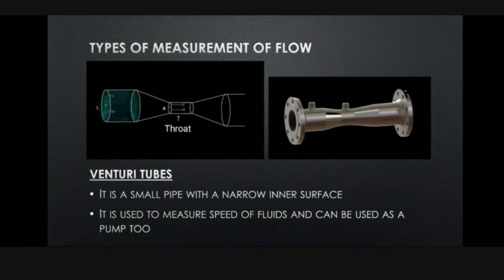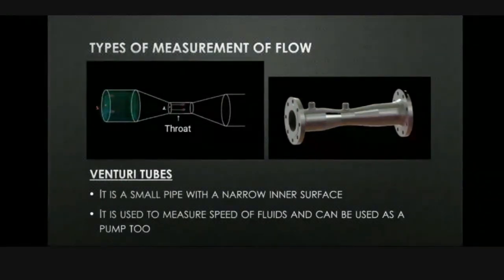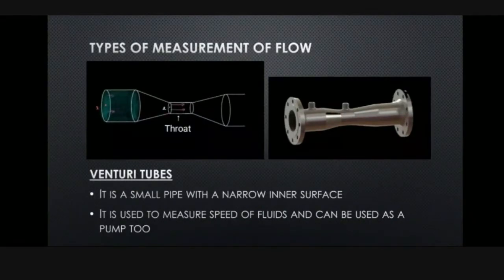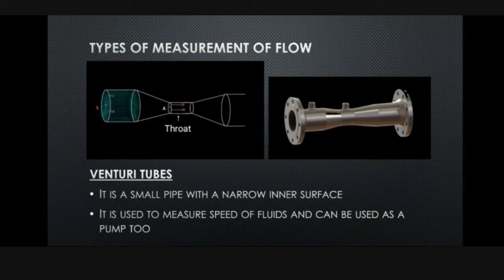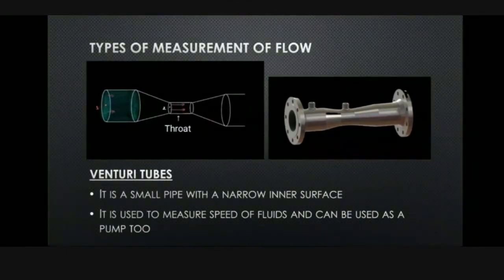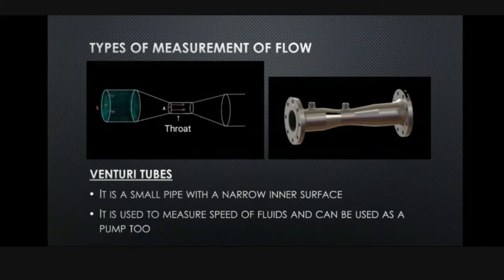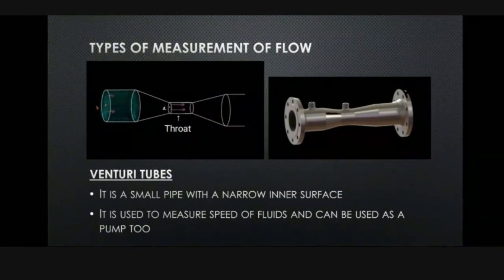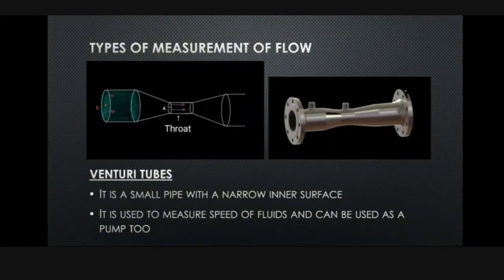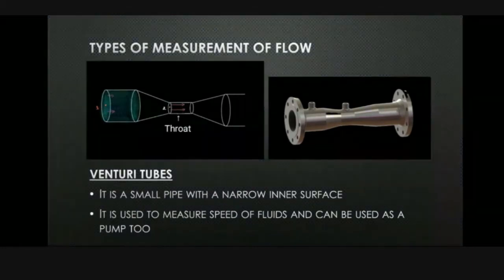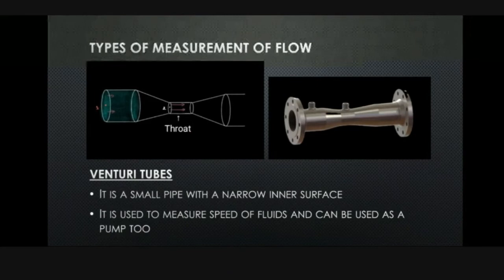The velocity of flow is higher at the throat. There, pressure energy converts into kinetic energy. In a venturimeter, there is a smooth entry of flow and smooth exit of flow at the throat as compared to the orifice plate meter. It works on Bernoulli's theorem. It is suitable for all types of liquid like slurries, abrasives, and liquid gases, etc. It is used in large diameter pipes, hence suitable for wastewater treatment plants. It also allows the flow of some solid particles.